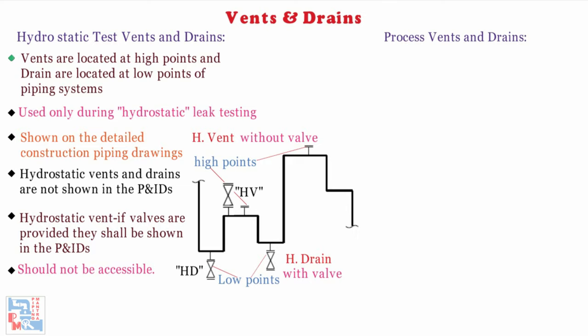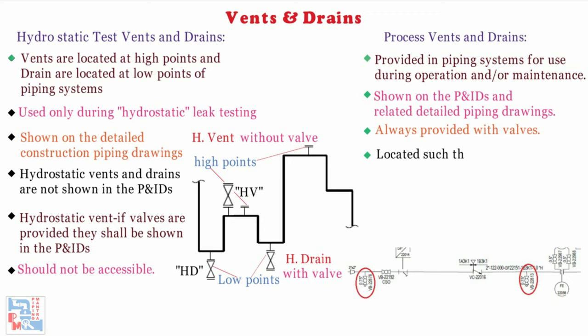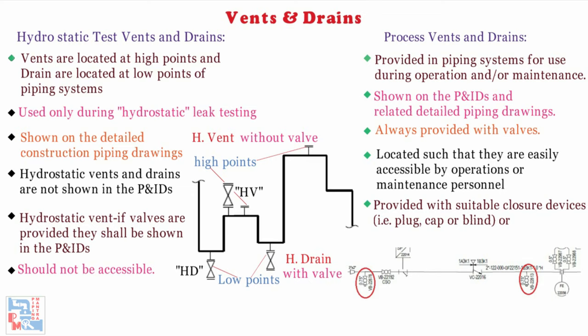Process vents and drain connections are provided in piping systems for use during operation and/or maintenance. These vent and drain connections are shown on the P&IDs and related detailed piping drawings. They are always provided with valves and are located such that they are easily accessible by operations or maintenance personnel. Such vents and drains may be provided with suitable closure devices, i.e., plug, cap, or blind, or may be connected to the vent or drain systems.